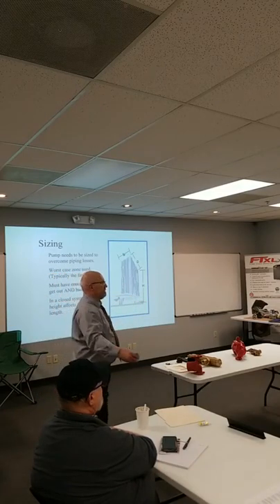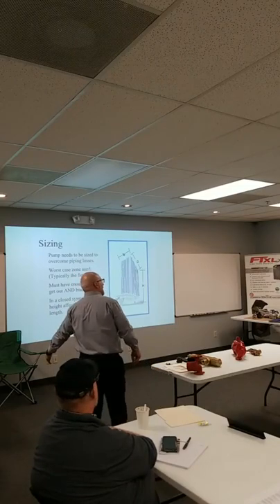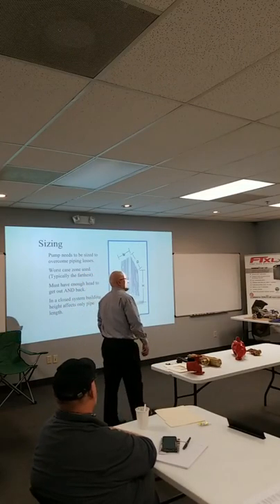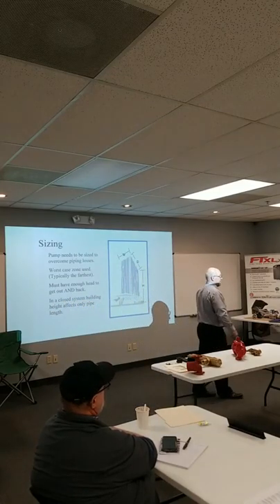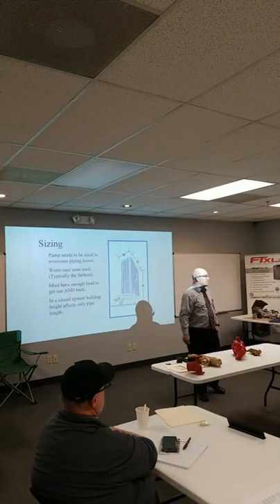What's the pump casing rated for, though? You do have to consider it at a certain height. Working pressure of 175 PSI. You're good there. Yeah. That's our standard pump. You're getting about 300 to 400 feet.